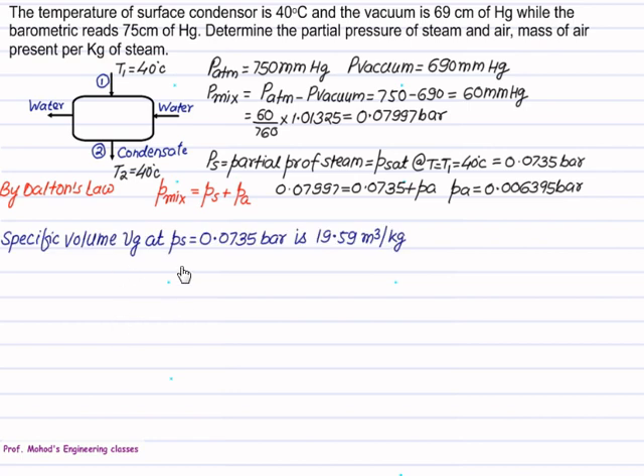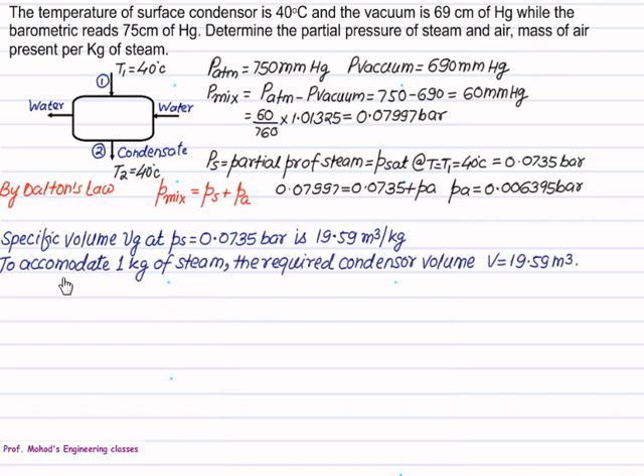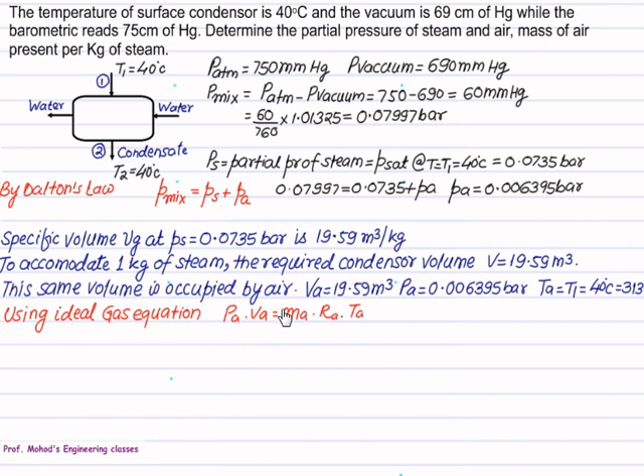The specific volume Vg at PS equals 0.0735 from steam table is 19.59 m³/kg. The specific volume indicates 19.59 m³/kg. So if you want to store 1 kg of steam, we require a condenser shell volume equal to 19.59 m³. And this volume is entirely filled by the steam as well as air. Since we know the partial pressure of air, volume of air, and gas constant of air, we can calculate mass of air for 1 kg of steam. So this same volume is occupied by air also. We can write the volume of air 19.59, but remember it is per kg of steam. Partial pressure of air is 0.006395 bar.